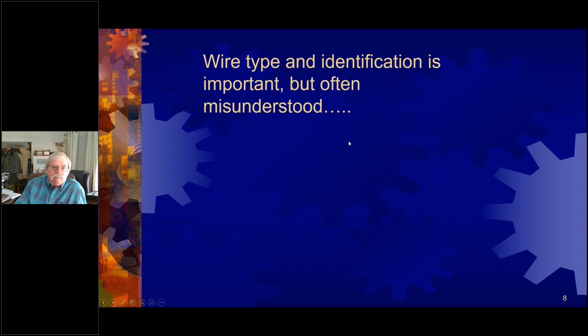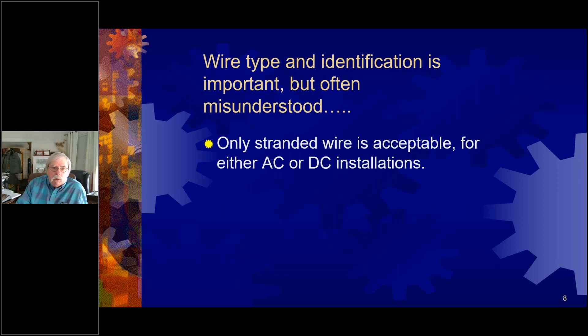Wire type and identification is important, often misunderstood. We only recommend stranded wire for either AC or DC installations. And one of the things I hear all the time, and it's sort of befuddling, is that we do not anywhere in our standards say that tinned wire must be used.